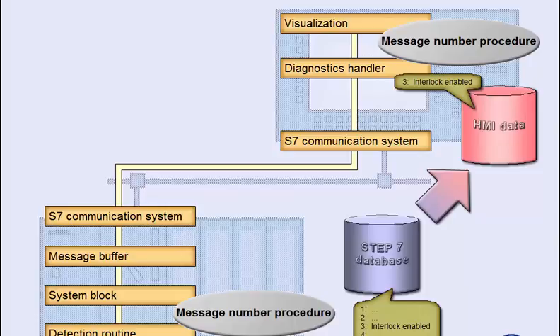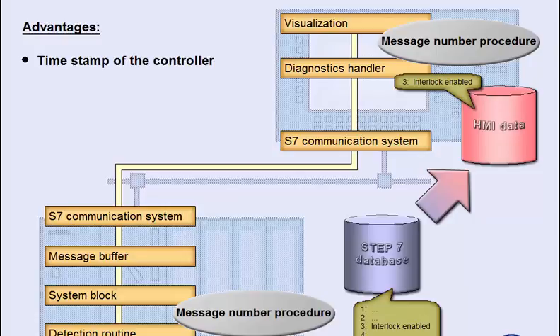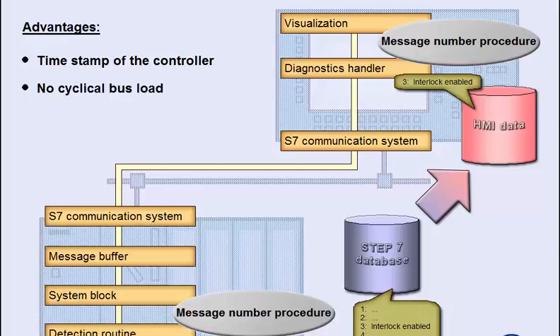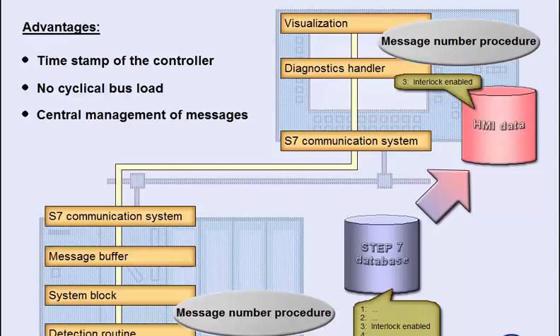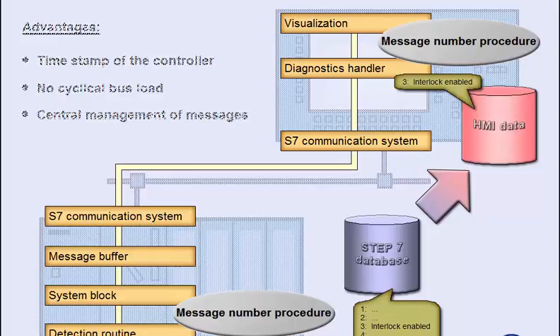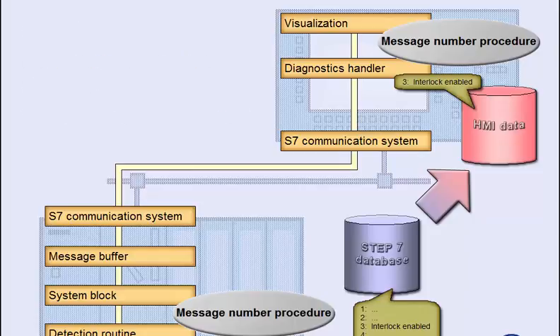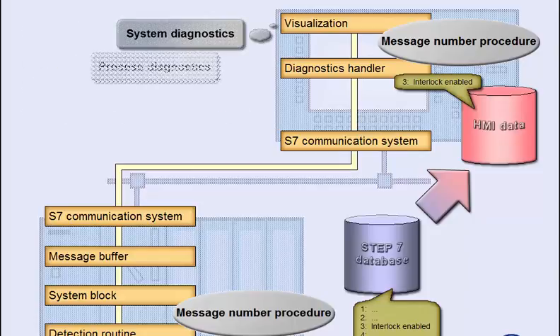In comparison to the bit or analog message procedure provided by the HMI system, the message number procedure in Step 7 has, for instance, the following advantages. The controller generates the timestamp right after the event. Messages are only transmitted if an event actually happens. Without such an event, they do not add to the busload. Since messages are centrally managed in the controller, they have the same status even if they appear on more than one operating device. All these advantages allow high-performance system and process diagnostics.